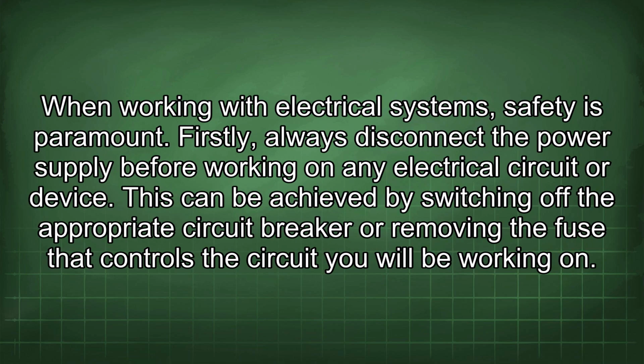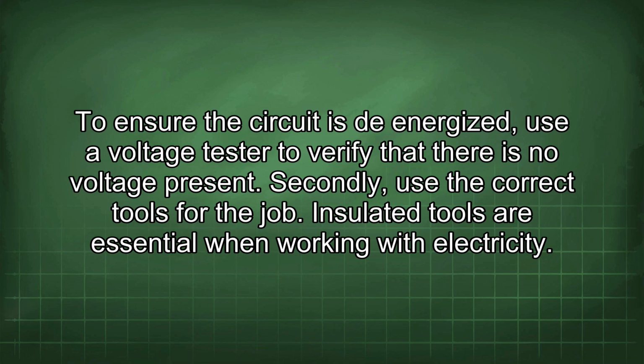When working with electrical systems, safety is paramount. Firstly, always disconnect the power supply before working on any electrical circuit or device. This can be achieved by switching off the appropriate circuit breaker or removing the fuse that controls the circuit you will be working on. To ensure the circuit is de-energized, use a voltage tester to verify that there is no voltage present. Secondly, use the correct tools for the job.